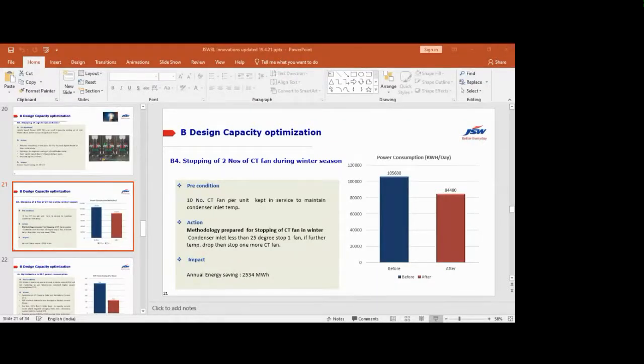And design capacity optimization: stopping of 2 CT fans during the winter season. We were running 10 CT fans, but in the winter season the ambient temperature comes down to 8 to 10 degrees. So we adopted a methodology: when the condenser inlet is less than 25 degrees, we stop one fan. If the temperature drops further, then we stop one more CT fan. By doing this, our annual energy saving is 2534 megawatt hour.